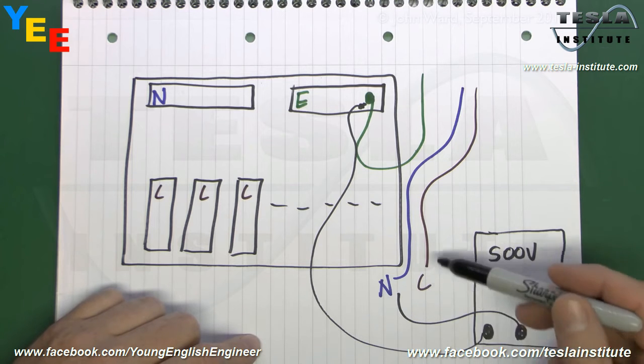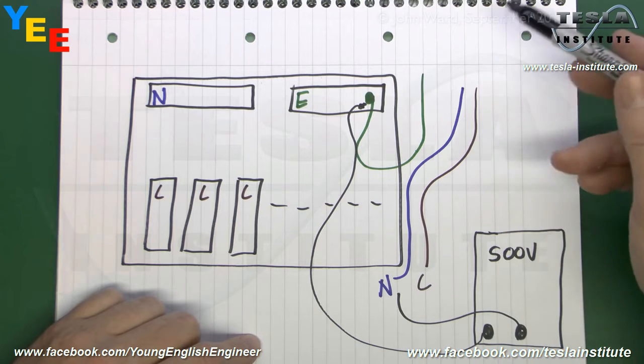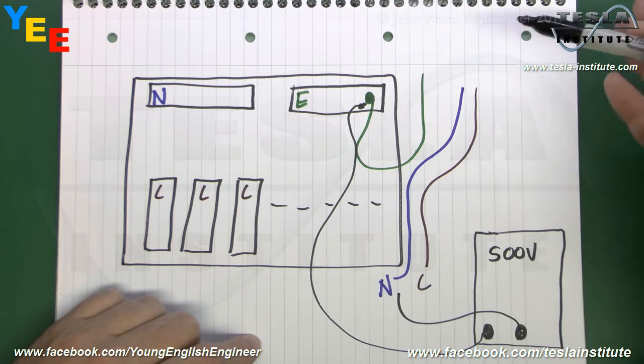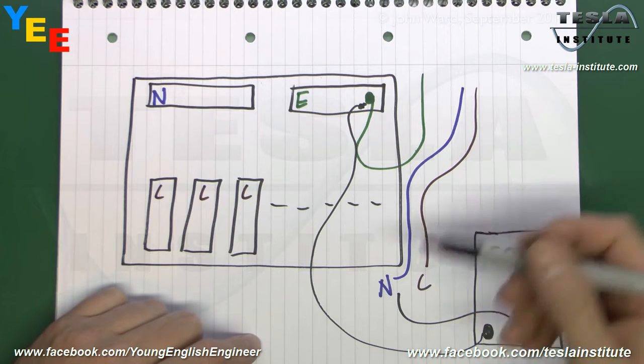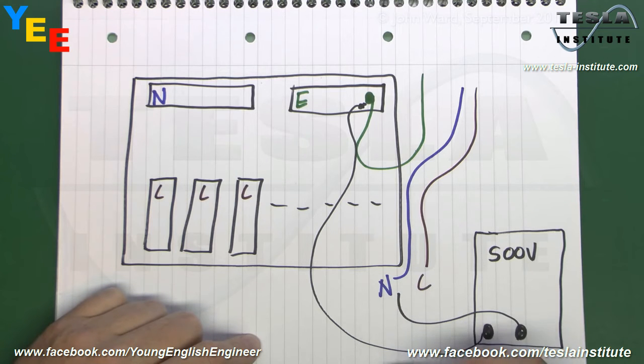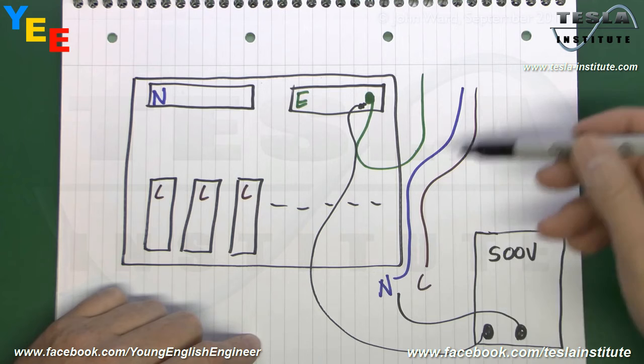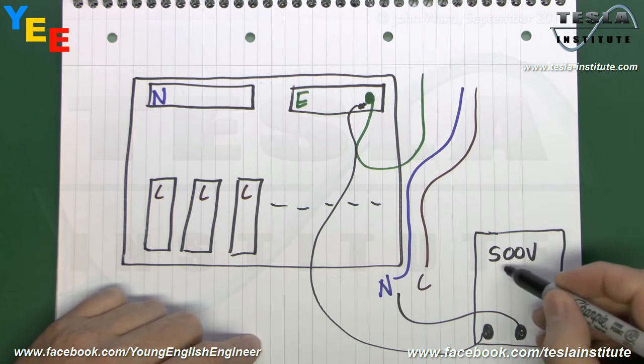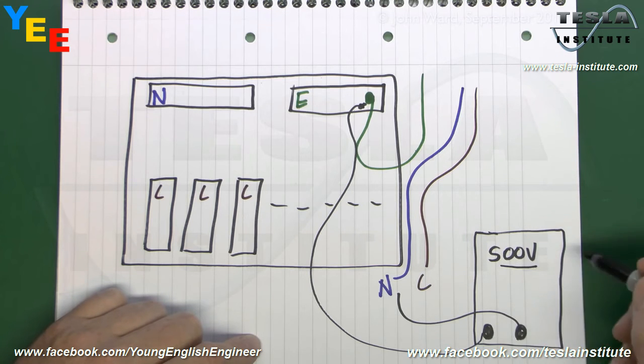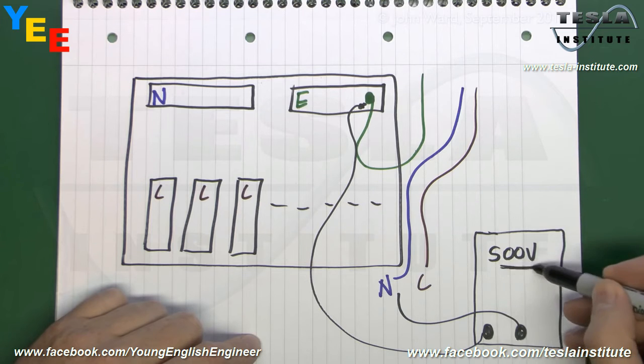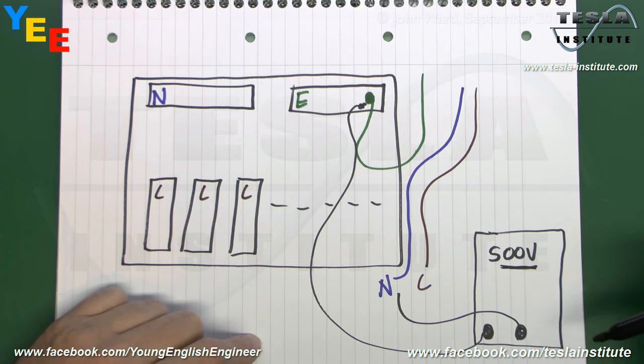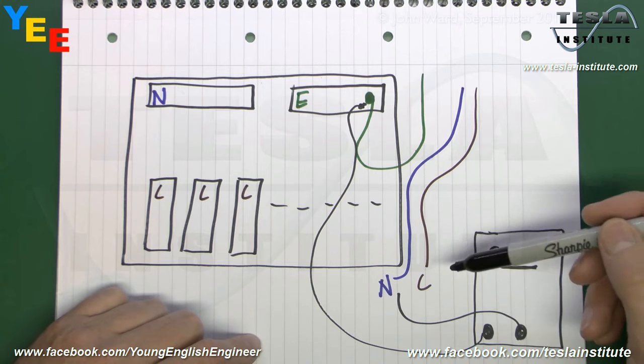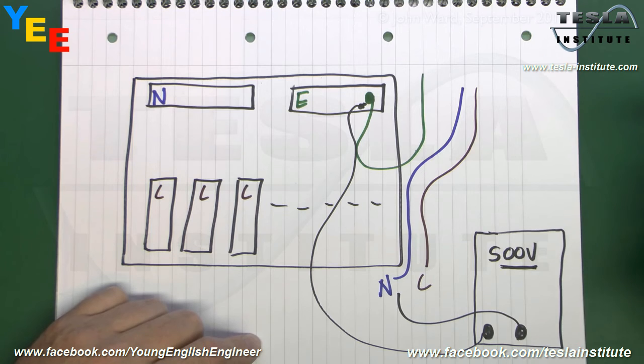However, this does require that the circuit doesn't have any kind of loads or anything attached to it, because of course if there's something attached at the end like a lamp or a piece of equipment, if you test between neutral and line, then it's going to show up as a fault because some of that current will be conducted through the equipment. And bearing in mind that if you're going to shove 500 volts in there, there are certain types of equipment which could theoretically be damaged by putting 500 volts DC into them, so not desirable to actually do that. So you do need to disconnect all of the equipment from the circuit before doing this test. And of course on a new circuit it wouldn't be connected yet anyhow.